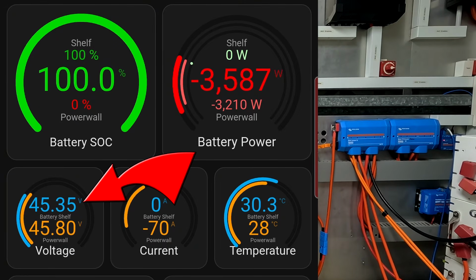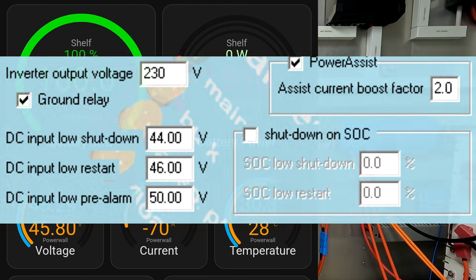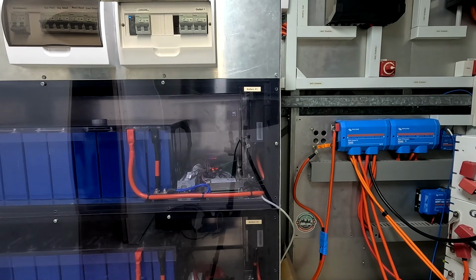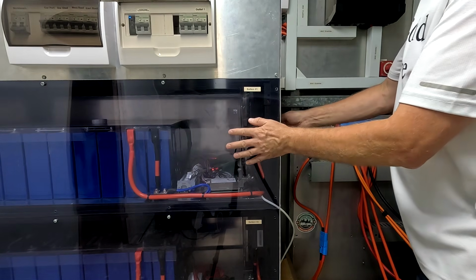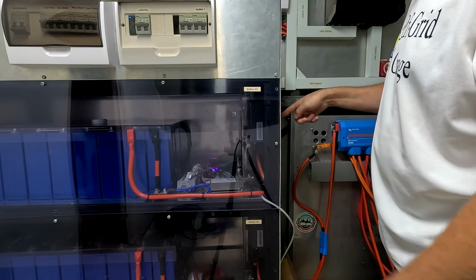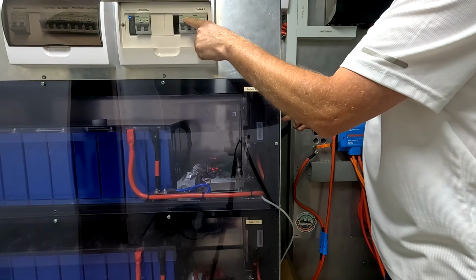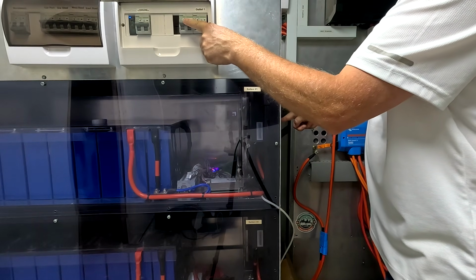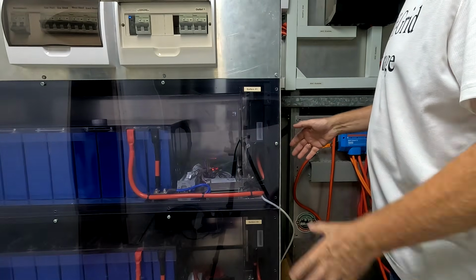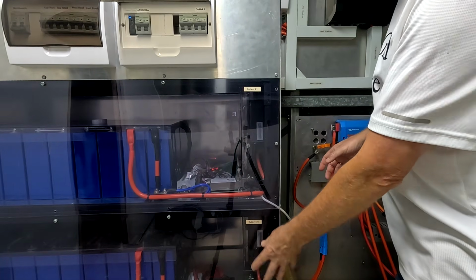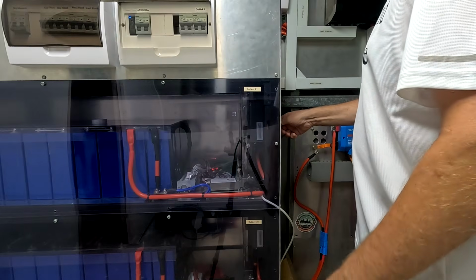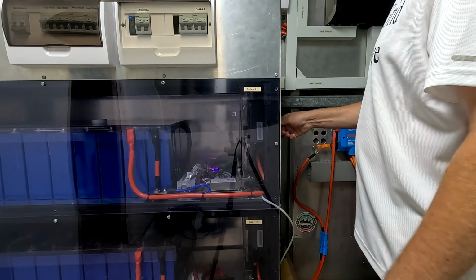So the multiplus just sees 45.35 volts. I think it turns off at 42 or something, so really low, but I don't want to wait until then. I think I'll switch over now to a dual system again, separating the shelf and the Powerwall. So I'm turning on the top shelf battery now with this circuit breaker, and a split second later I'm turning off the 63 amp circuit breaker, which separates the two systems again. Then the multiplus will run from this system. I'll turn on the other batteries from the battery shelf as well, and we will keep running the other inverter, the Phoenix, from the MB56.